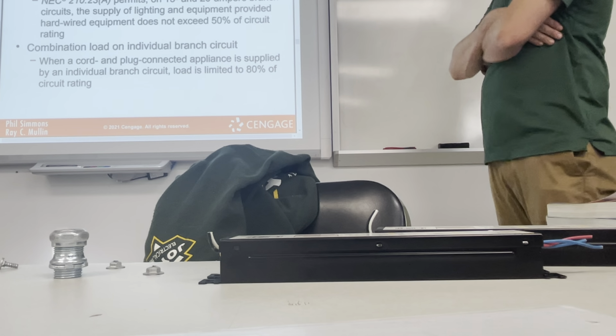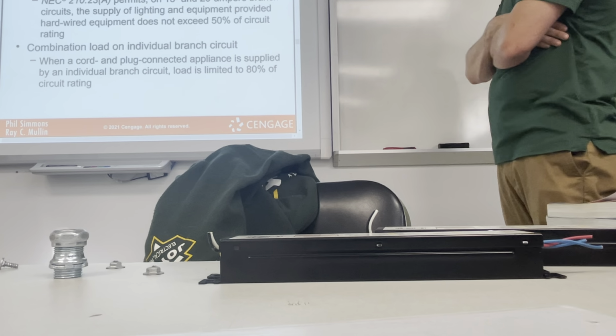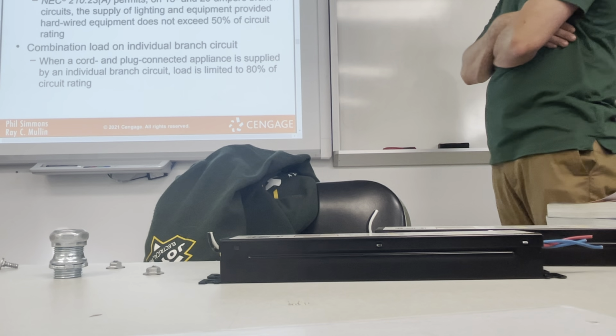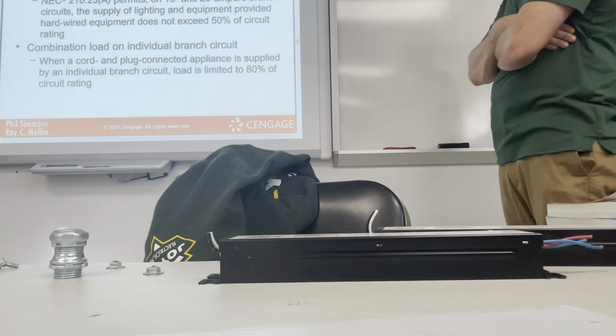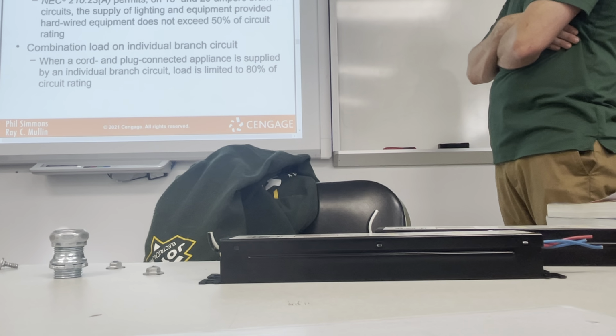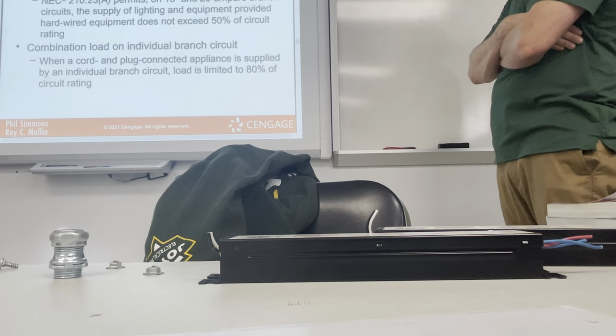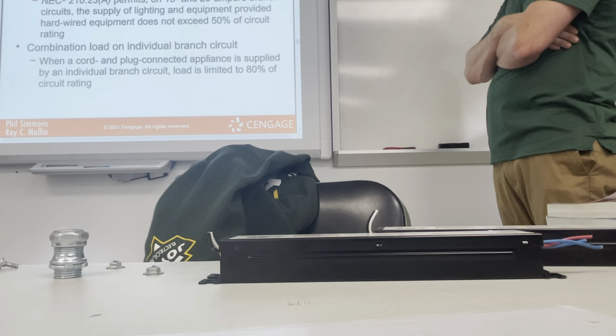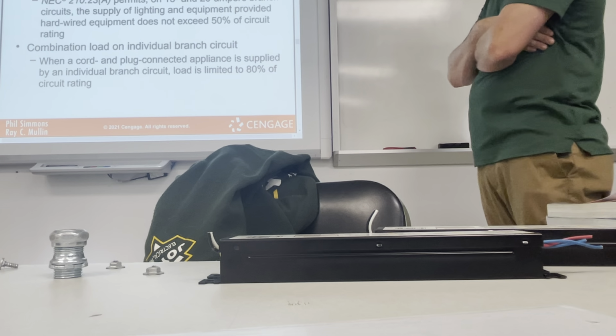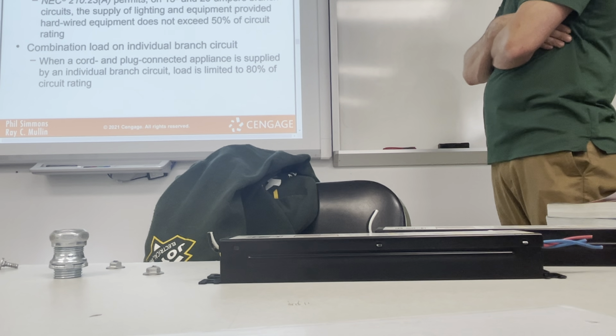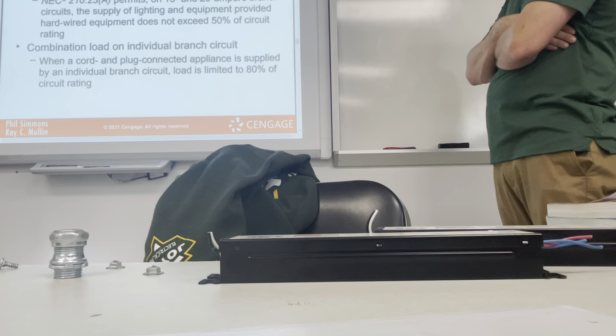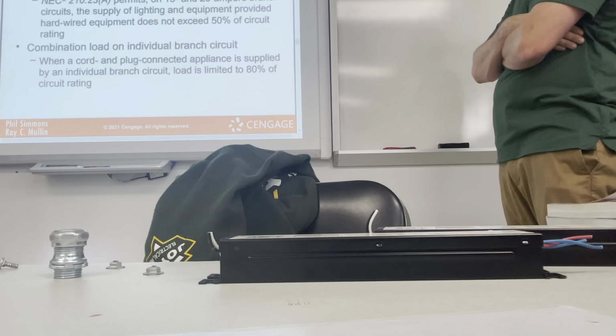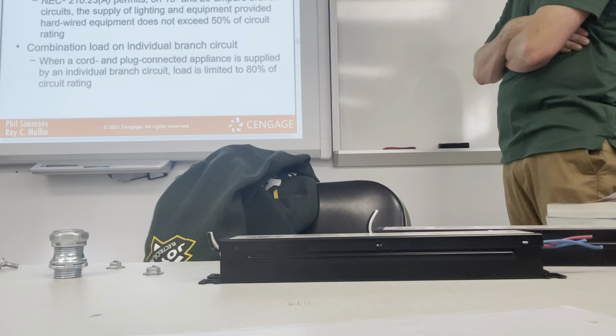Equipment and lighting on a branch circuit. NEC 210.23(A) permits, on 15 and 20 ampere branch circuits, the supply of lighting and equipment, provided hardwired equipment does not exceed 50% of the circuit rating.